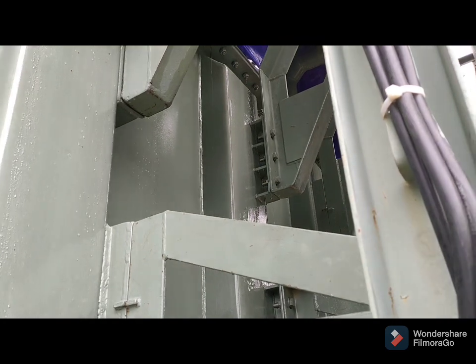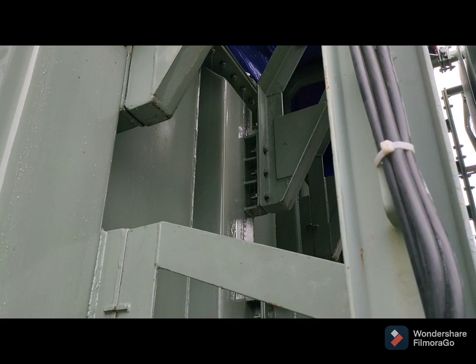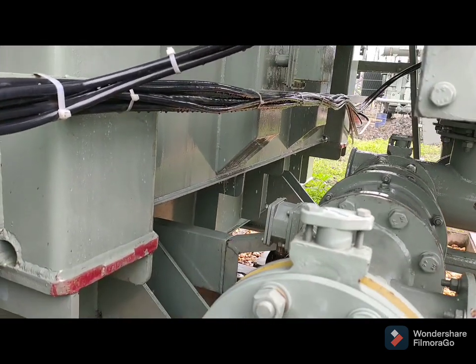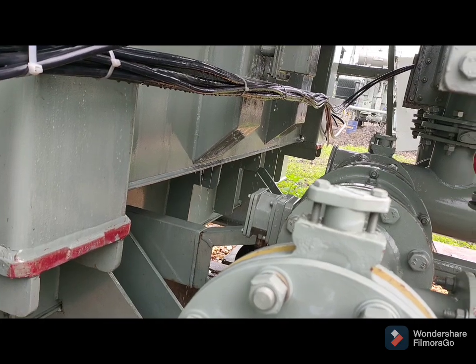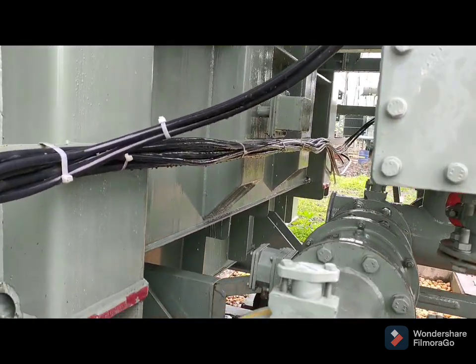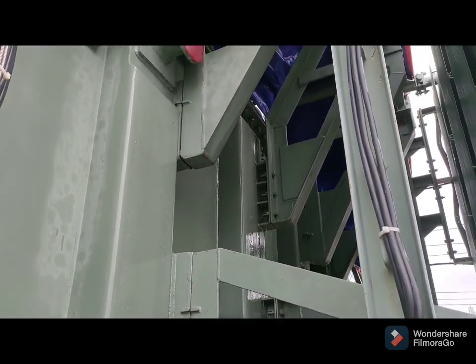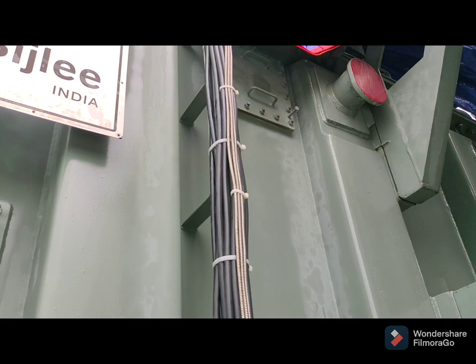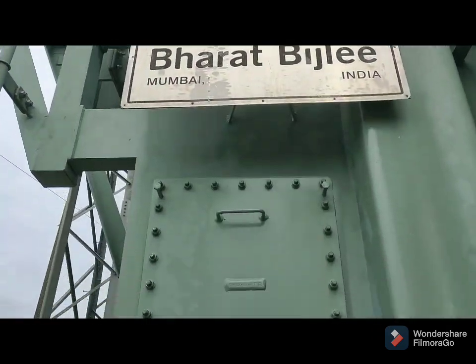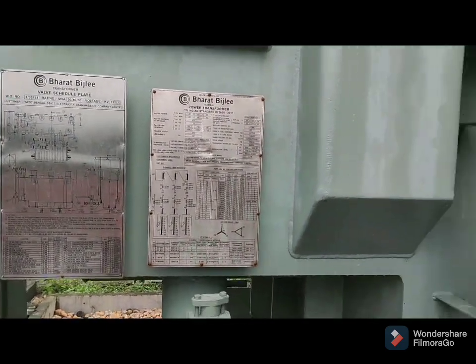These are all the videos about how the oil is just coming out from the transformer after the fault happened — conservator oil and radiator oil, up to the top level, up to the main tank top level. The top cover oil has been drained out after the fault, because after the huge amount of fault, huge amount of gas formation occurred, PRD operated, and the Buchholz relay made the transformer trip.